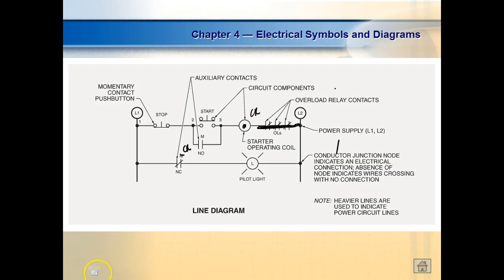So we got energy sitting right here. It's coming down here, sitting right there, but it's got nowhere to go. This guy's coming flying through - that's a normally closed contact, so it comes through. And we got both wires now - both L1 and L2 connected across the light, so the light should be on, right? Everybody understand that? So what do we do?